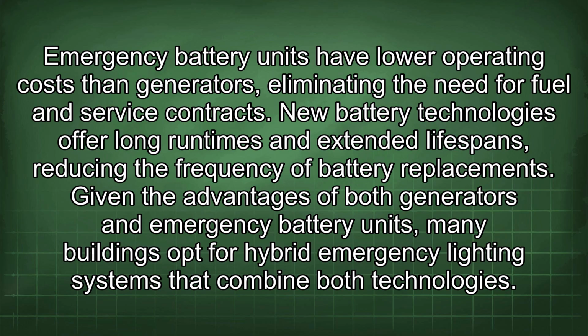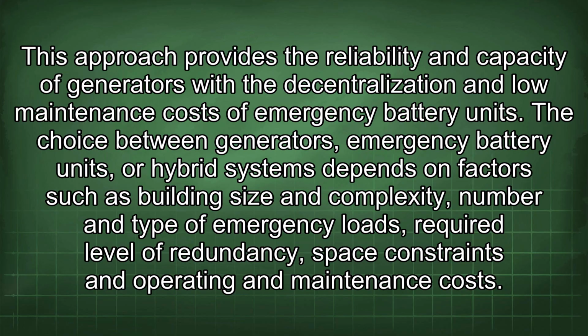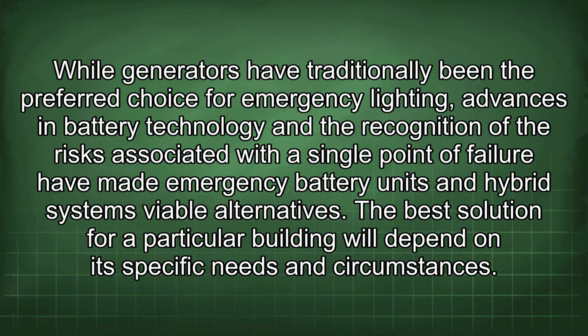Given the advantages of both generators and emergency battery units, many buildings opt for hybrid emergency lighting systems that combine both technologies. This approach provides the reliability and capacity of generators with the decentralization and low maintenance costs of emergency battery units. The choice between generators, emergency battery units, or hybrid systems depends on factors such as building size and complexity, number and type of emergency loads, required level of redundancy, space constraints, and operating and maintenance costs. While generators have traditionally been the preferred choice for emergency lighting, advances in battery technology and the recognition of the risks associated with a single point of failure have made emergency battery units and hybrid systems viable alternatives. The best solution for a particular building will depend on its specific needs and circumstances.